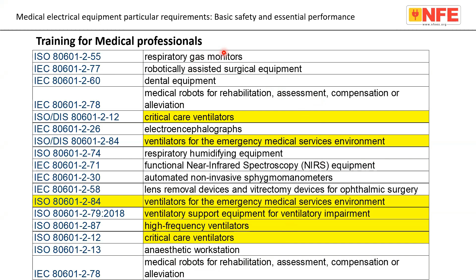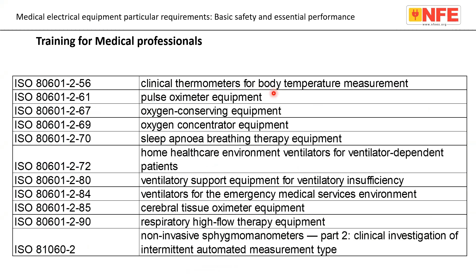So, for example, the subject 1, medical equipment, I am just showing you the type of equipment on the right side and the reference standard. So our training will include educating the biomedical engineer about the safety requirements of these different electro-biomedical equipment. And for example, if we look at the ventilator alone, there are several kinds of ventilators available. For example, critical care ventilator, ventilator for emergency medical service, high frequency ventilators, and so on.